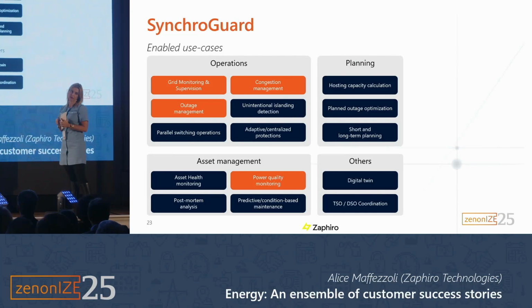The first module is the observability module. Through state estimation, we provide observability in all the grid in real time, so we can integrate renewables, check congestions, and so on and so forth. Then outage management is the other important module that we have. We provide fault detection and fault location, helping corrective maintenance and reducing the intervention time, so SAIDI and SAIFI. We also provide information about power quality. And thanks to this power quality module, we also enable a 4th module, predictive maintenance. Based on power quality events, we can extend the lifetime of the assets and also calculate some time to failure for the equipment.